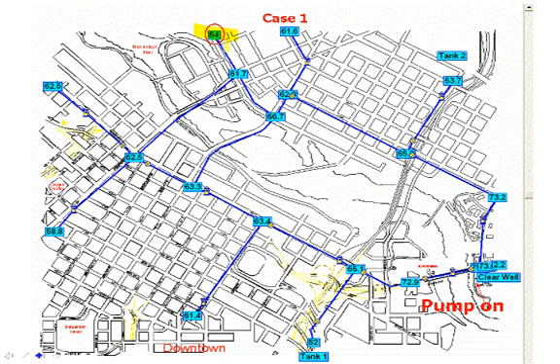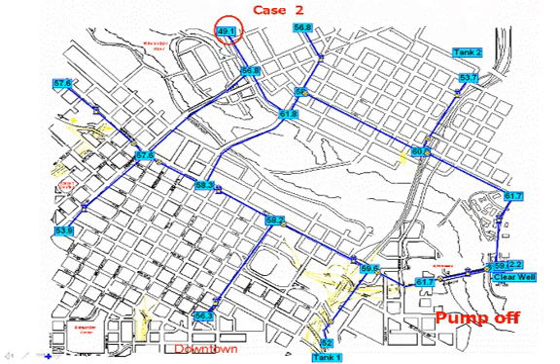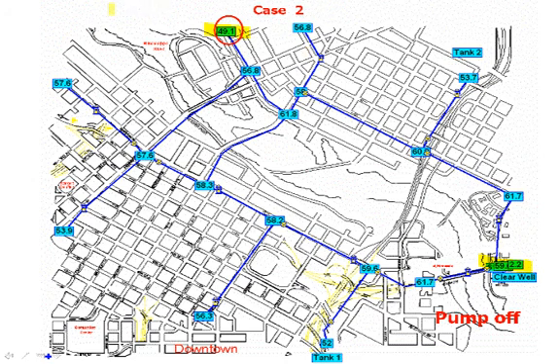With the pumps operating, the lowest pressure out here is 54 PSI. Near the pump station, it's around 73. With the pumps off, around the pump station the pressure drops down to the 50s, and here the pressure drops about 5 PSI. So the tanks are supplying the system quite adequately.